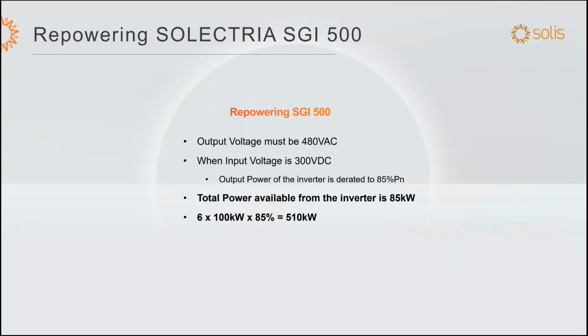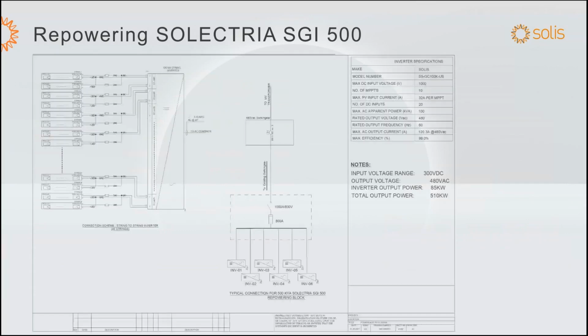A similar example as before. And then the single line, kind of the same approach here, showing a little bit different approach. This is actually an actual site that we will do in a proposal. We keep the existing 800 amp circuit breaker.